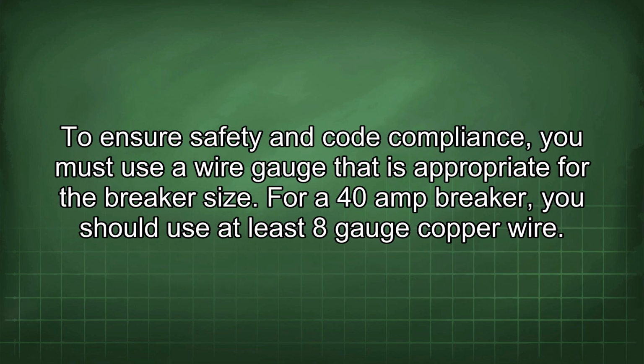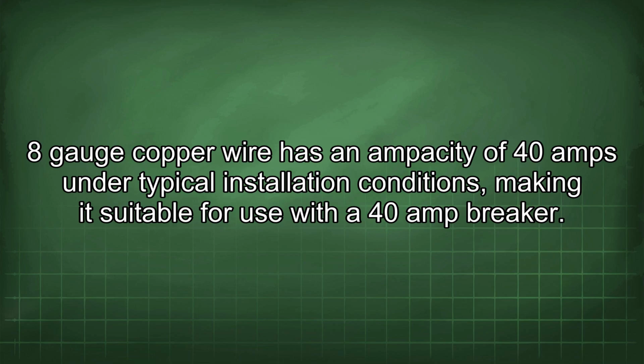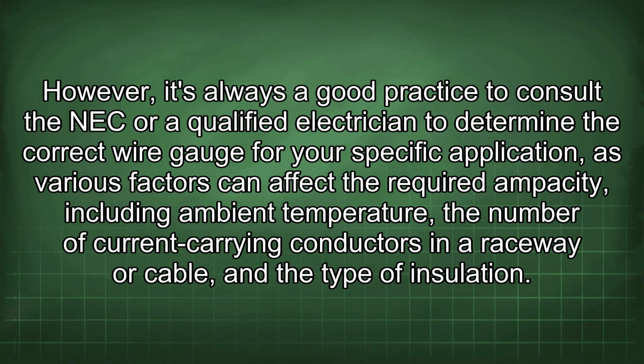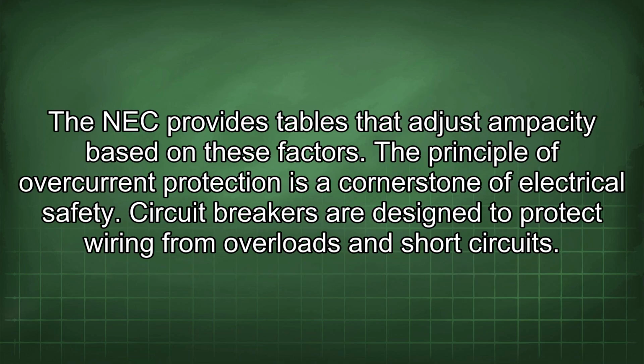To ensure safety and code compliance, you must choose a wire gauge that is appropriate for the breaker size. For a 40-amp breaker, you should use at least 8-gauge copper wire. 8-gauge copper wire has an ampacity of 40 amps under typical installation conditions, making it suitable for use with a 40-amp breaker. However, it's always a good practice to consult the NEC or a qualified electrician to determine the correct wire gauge for your specific application, as various factors can affect the required ampacity, including ambient temperature, the number of current carrying conductors in a raceway or cable, and the type of insulation. The NEC provides tables that adjust ampacity based on these factors.